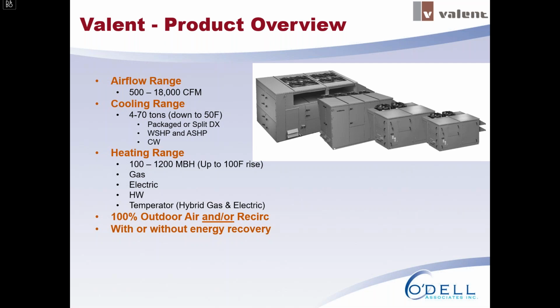On the heating side, we have anywhere from 100 to 1200 MBH of heating, up to 100 degree temperature rise. And then we have all manner of different heating sources, whether that be gas, electric, hot water, or steam. And then there is another solution called the Temperator, which is a hybrid of gas and electric. This is a solution that I felt was an excellent fit for labs and areas where you needed very tight control of temperature in spaces. We are starting to also see some interest in the hybrid gas and electric units from customers looking to reduce greenhouse gases, but not wanting to overtax the electrical on their building.